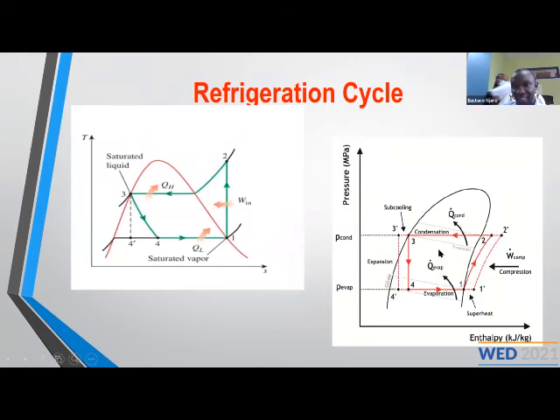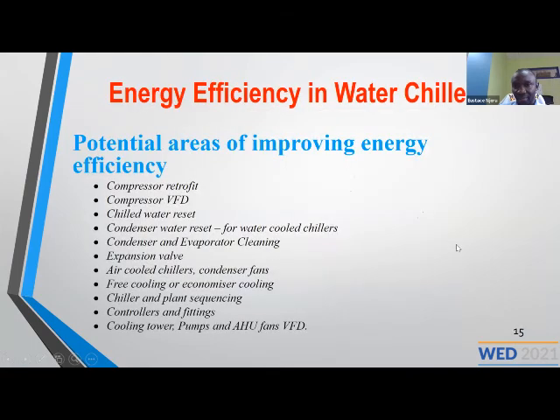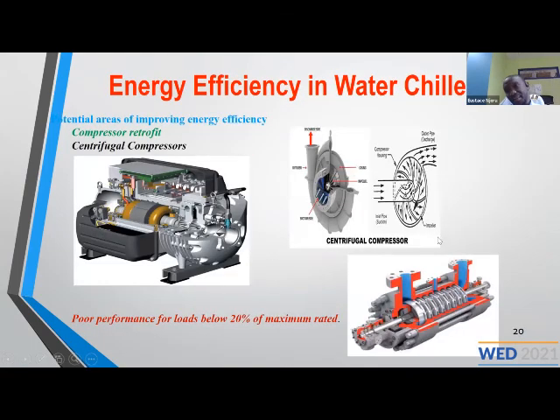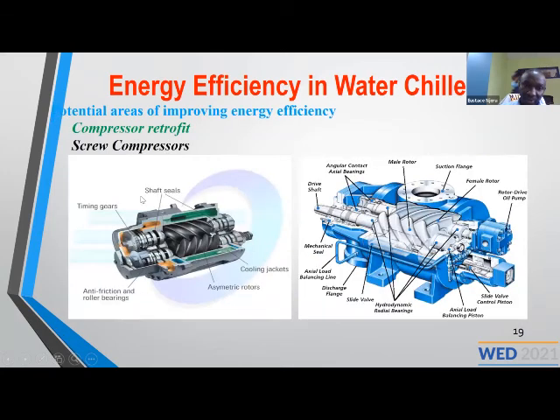So in this case, that's why we sometimes employ a two-stage semi-hermetic. These are the screw compressors. As you have seen, they are better between 150 and 750 cooling tons. They employ a screw, and they can easily be controlled by a VFD because they are not reciprocating. They don't have as many moving parts as the reciprocating compressors, so they are more efficient than the reciprocating.